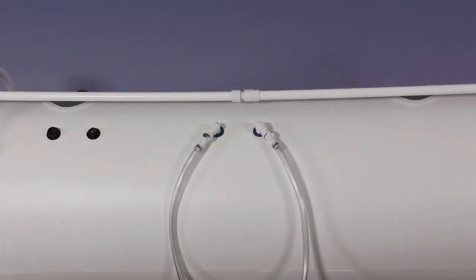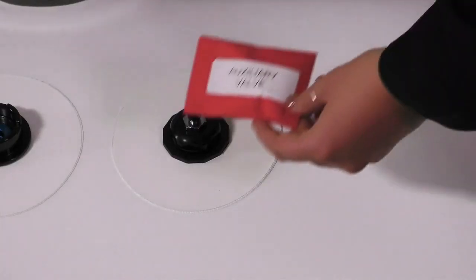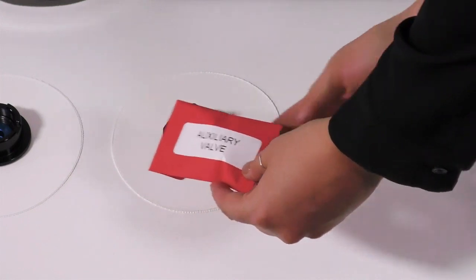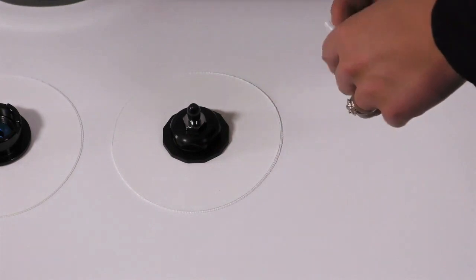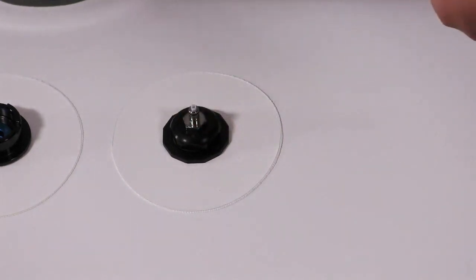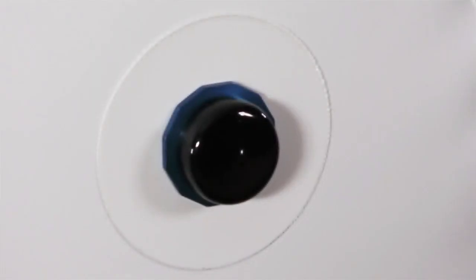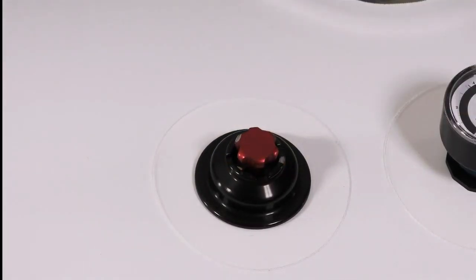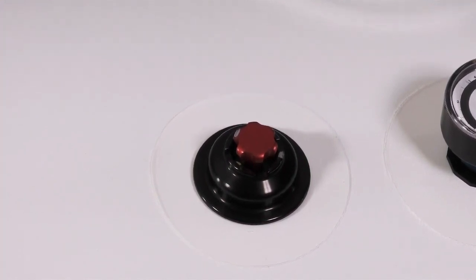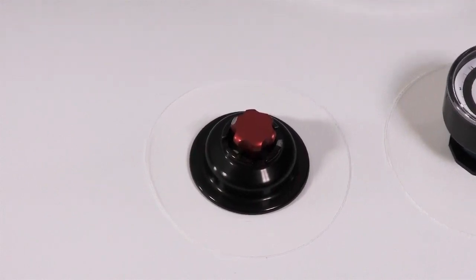On the back of the chamber there are 2 fill valves. Next to the window is an auxiliary port where the auxiliary valve attaches. This small auxiliary valve is located in your packet along with the zipper cleaner, zipper lubricant, and thumb drive. There are also 2 additional ports, one at each end of the chamber. These are for additional accessories. The red deflation valve is designed to turn in either direction to release air from the chamber. This valve can also be used during pressurization to customize the speed of inflation for greater comfort and to aid in the equalization of ear pressure.